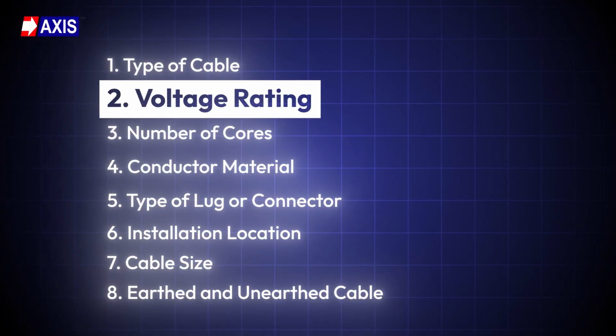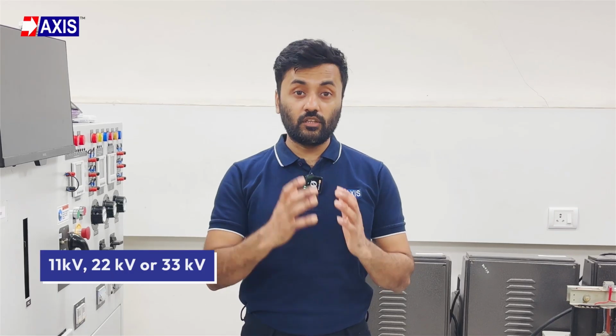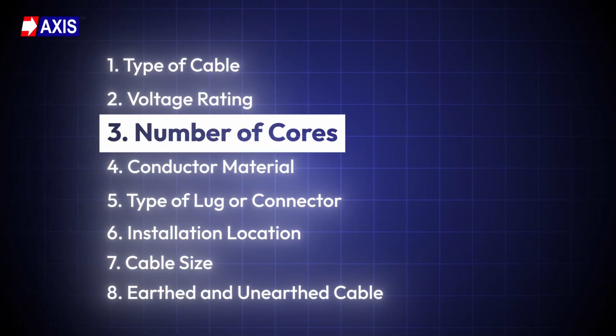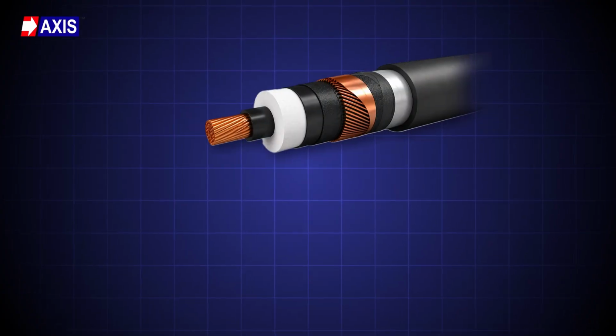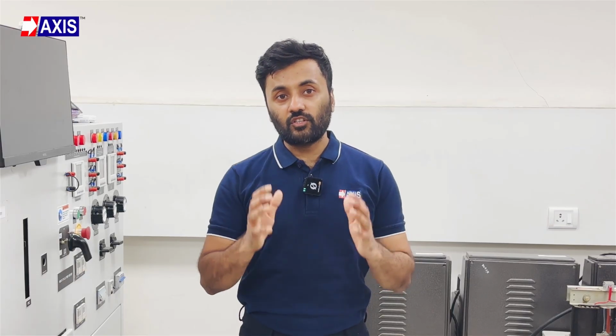Secondly, voltage rating. You must know the system voltage of your cable, for example 11 kV, 22 kV or 33 kV. Termination kits are designed for specific voltage classes because they must control the electric field and maintain insulation at the cable end. Thirdly, number of cores. Check whether your cable is single core or 3-core. Single core cables require separate terminations for each phase. 3-core cables require additional components to separate and seal the cores at the crutch area.